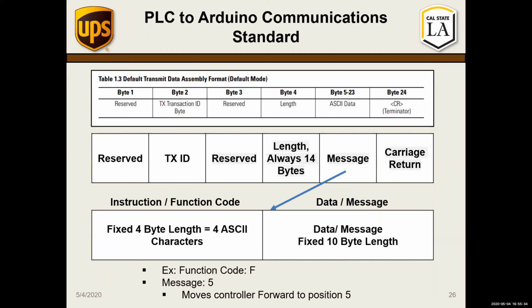Taking inspiration from the Modbus protocol's message structure, I set some new standards. I always use a fixed length, because this frame format doesn't have a built-in error check, so having a fixed length helps ensure we're not losing information and have a good message. Within that message, I broke it into two components: first a function code, then the actual message. The function code is 4 ASCII characters that can detail many different instructions, followed by the message itself. For example, to instruct a motor to move forward, I could send the ASCII character F along with the number 5, meaning move motor controller forward to position 5.